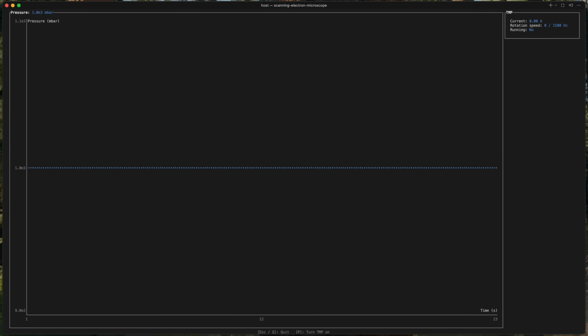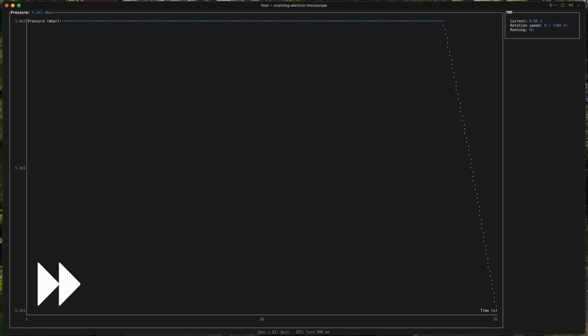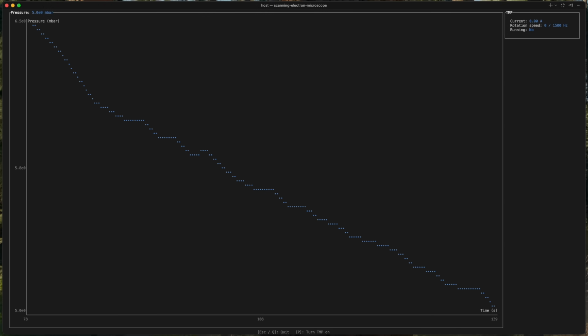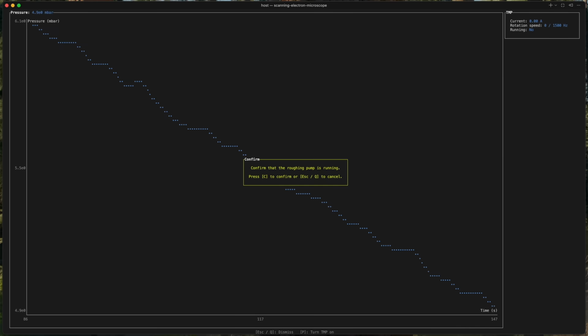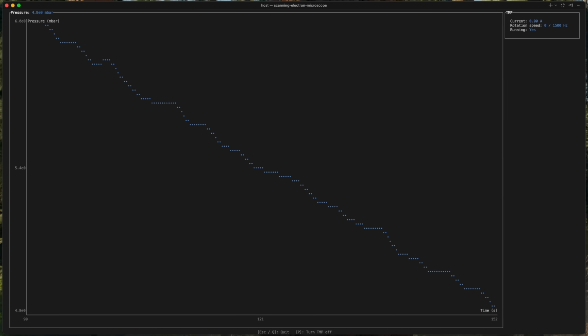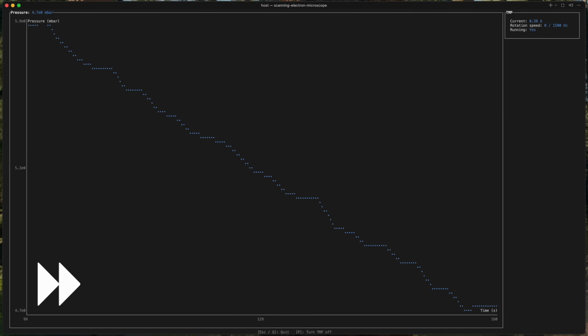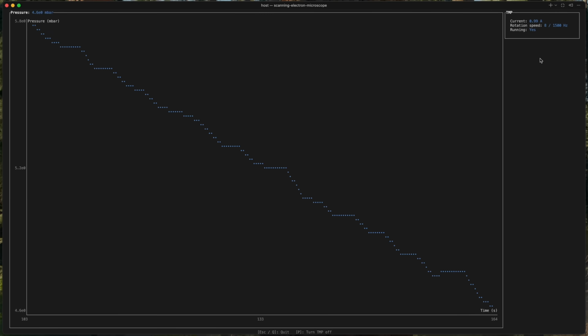I'll turn on the roughing pump and wait for the pressure to drop. So we can see that the pressure is dropping, but this graph has very quickly become useless. We can see the current pressure up the top left here, and around 15 seconds after turning the roughing pump on, we're already below the turbo's maximum operating pressure. After 2 minutes, the y-axis is updated, so the graph is a little more useful, and we're sitting at around 5 millibar. Let's turn the turbo on. It's asking me to confirm that the roughing pump is running, which it is. We can see the turbo started drawing a current and its rotation speed is increasing.